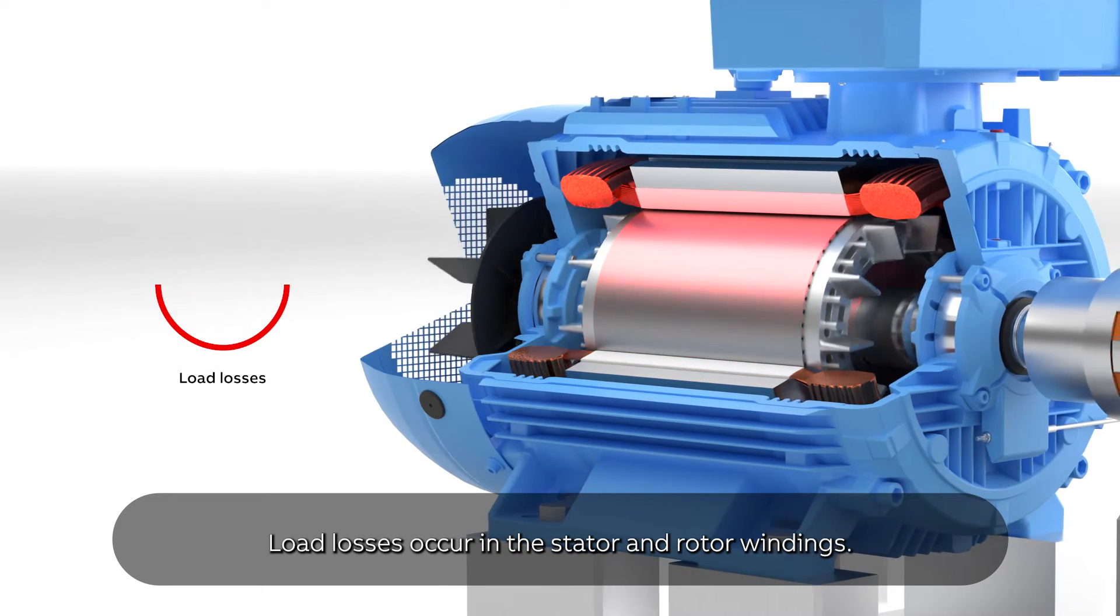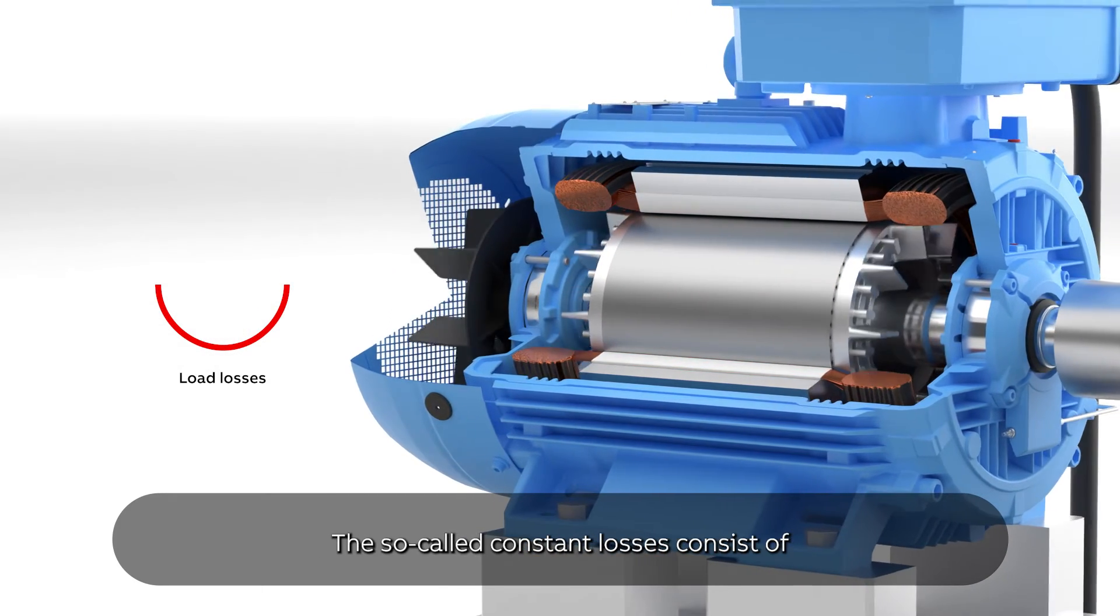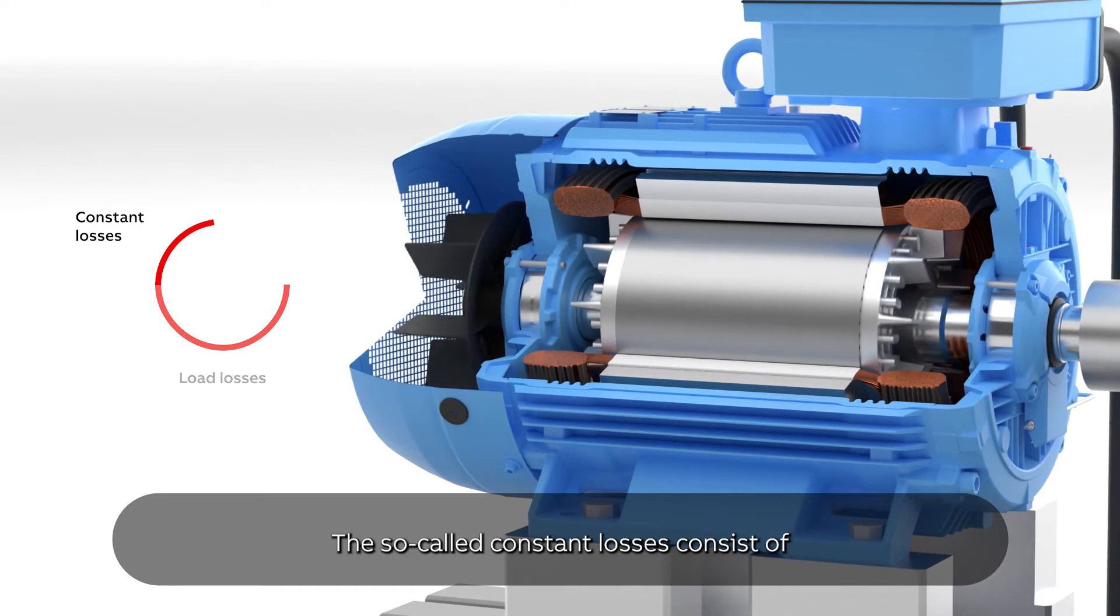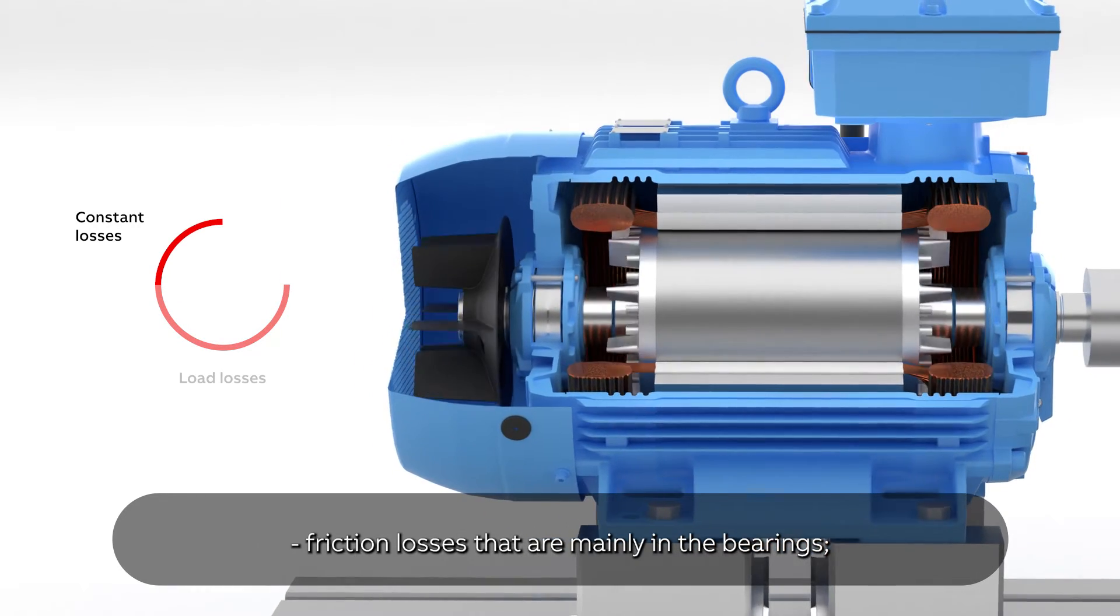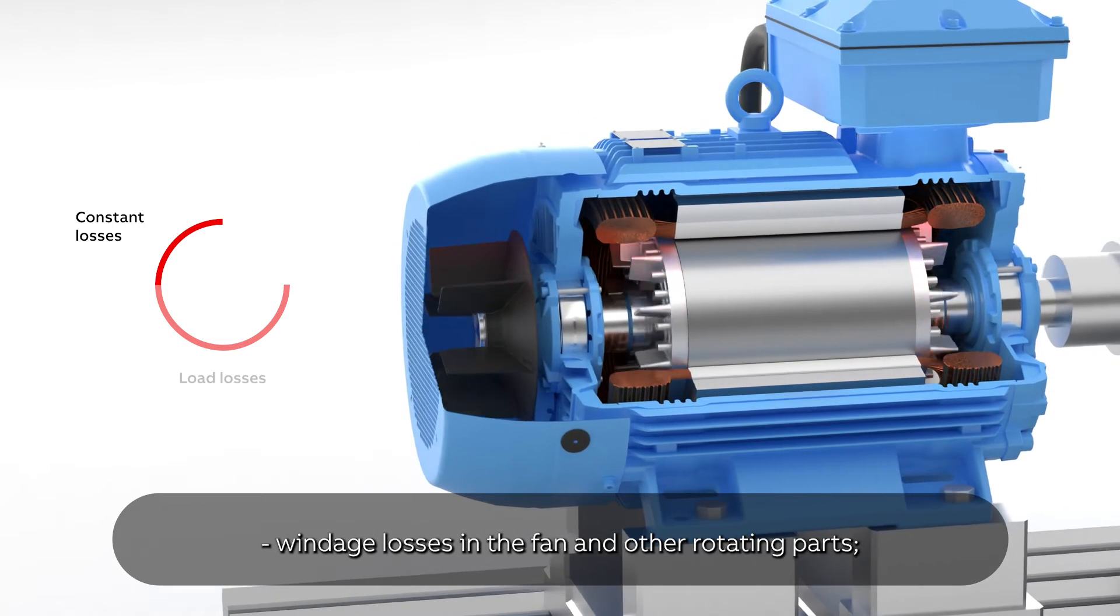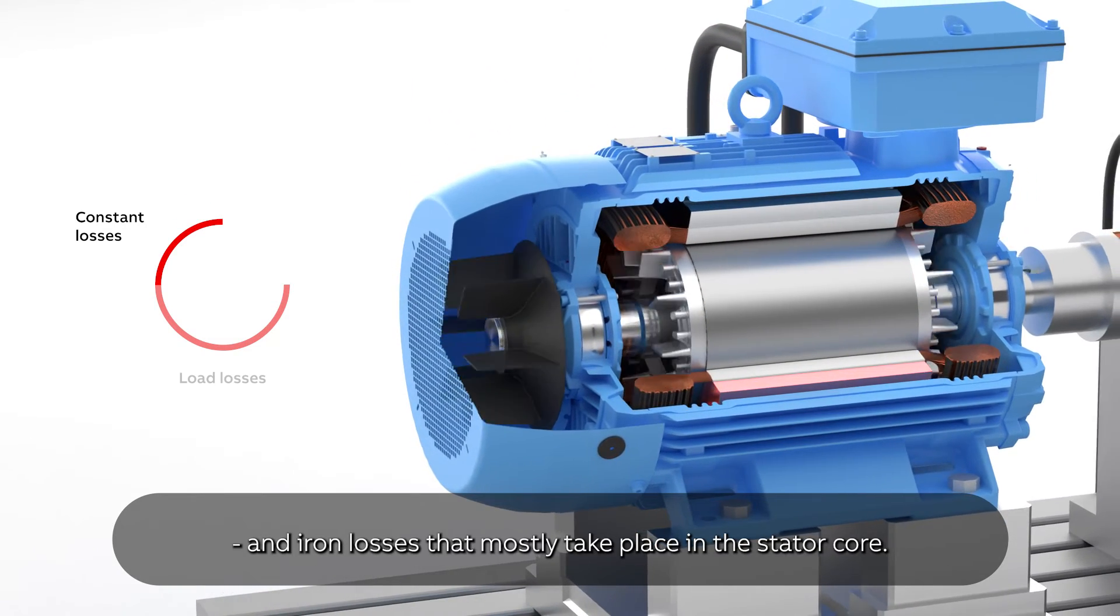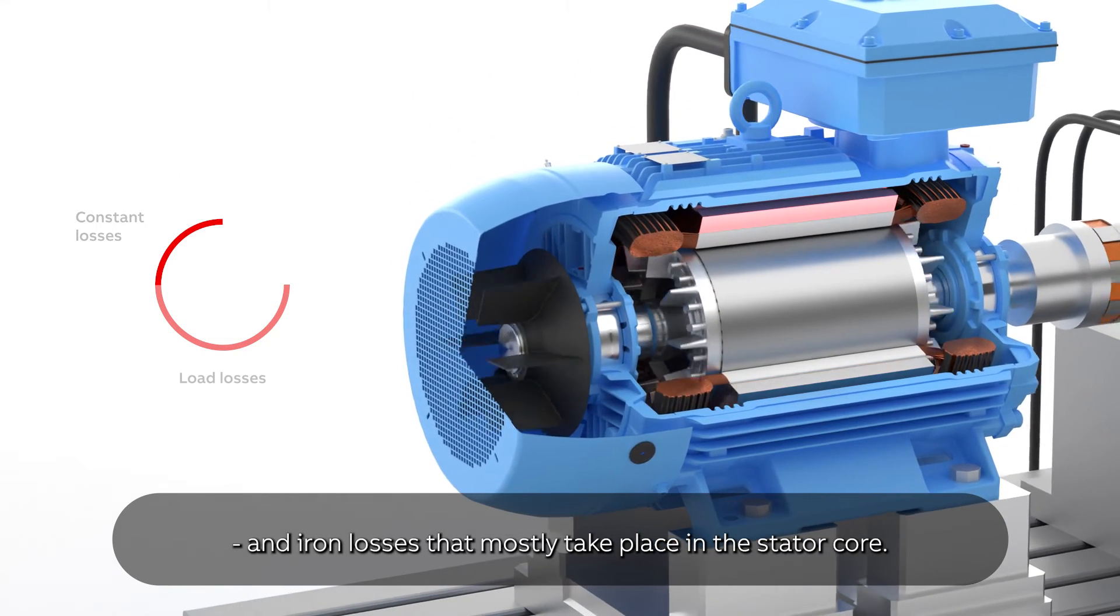Load losses occur in the stator and rotor windings. The so-called constant losses consist of friction losses that are mainly in the bearings, windage losses in the fan and other rotating parts, and iron losses that mostly take place in the stator core.